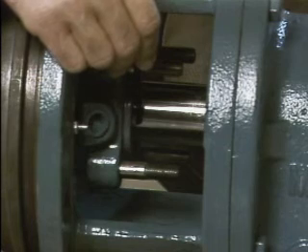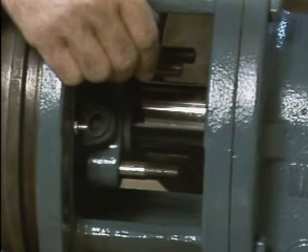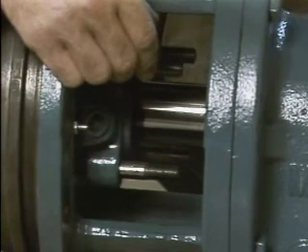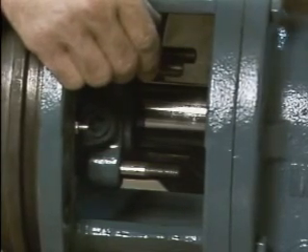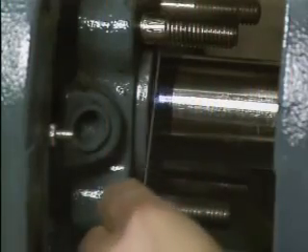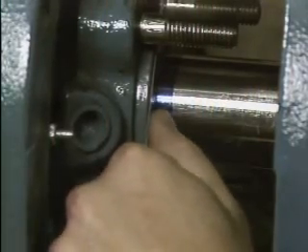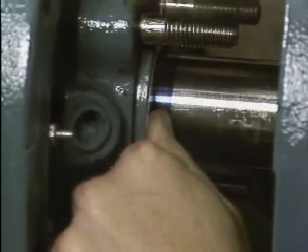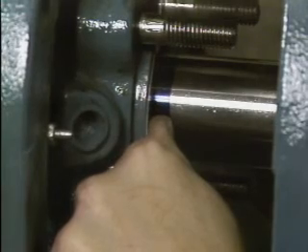After the impeller clearance has been measured, the shaft sleeve is marked so that the rotating element can be positioned properly later. This is done by first applying bluing to the shaft sleeve along the edge of the stuffing box. Then a line is scribed in the bluing to mark the edge of the stuffing box. This line is a reference line for positioning the seal's rotating element.